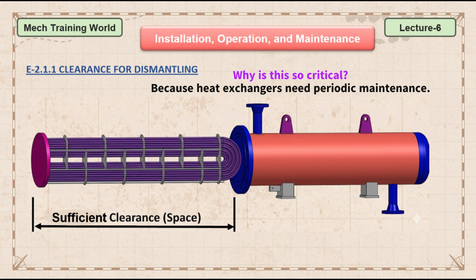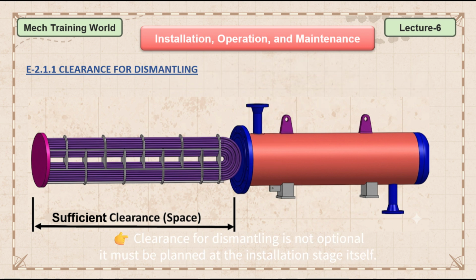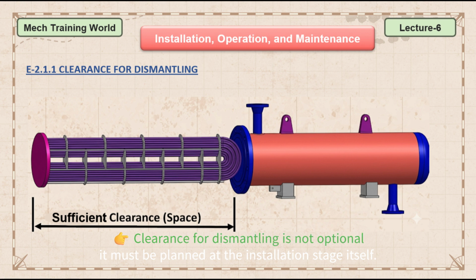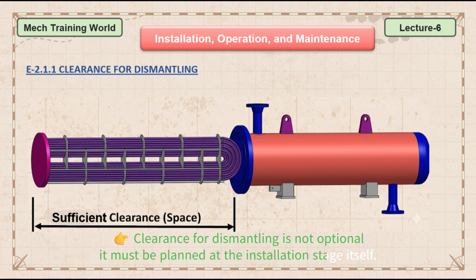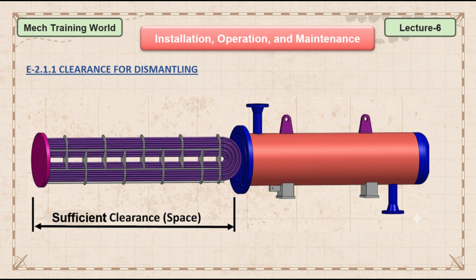Why is this so critical? Because heat exchangers need periodic maintenance. Tube leakage, fouling, or corrosion means the tube bundle must come out. If adequate clearance was not planned, maintenance becomes extremely difficult or sometimes impossible without dismantling nearby equipment. So always remember, clearance for dismantling is not optional. It must be planned at the installation stage itself. Once the heat exchanger is installed, there is no second chance.